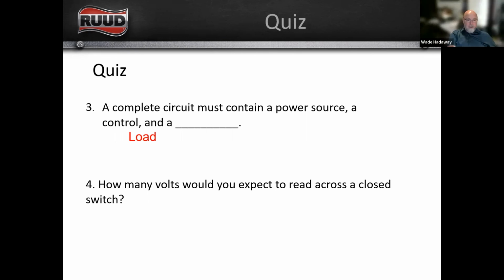How many volts would you expect to read across a closed switch? How many volts are we going to read across a closed switch? Zero. If you're reading any voltage across your closed switch, you've got a problem. You're dropping volts. You've got too much resistance across that switch.